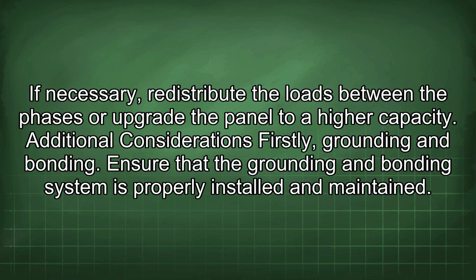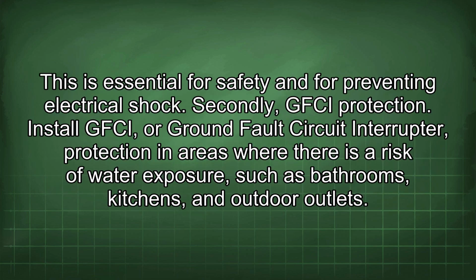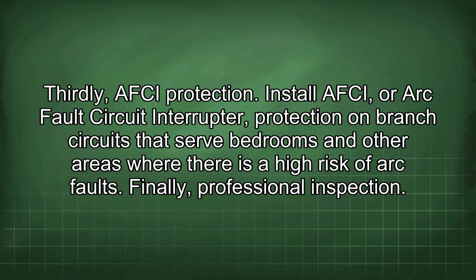Additional considerations. Firstly, grounding and bonding. Ensure that the grounding and bonding system is properly installed and maintained. This is essential for safety and for preventing electrical shock. Secondly, GFCI protection. Install GFCI, or ground fault circuit interrupter, protection in areas where there is a risk of water exposure, such as bathrooms, kitchens, and outdoor outlets. Thirdly, AFCI protection. Install AFCI, or arc fault circuit interrupter, protection on branch circuits that serve bedrooms and other areas where there is a high risk of arc faults.